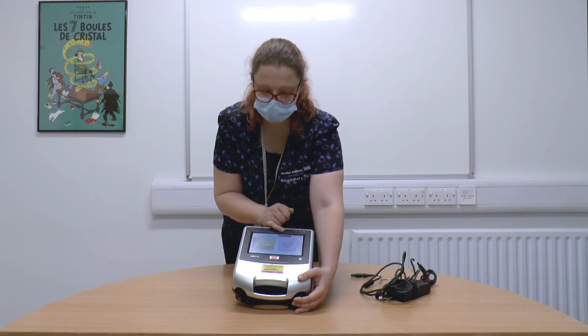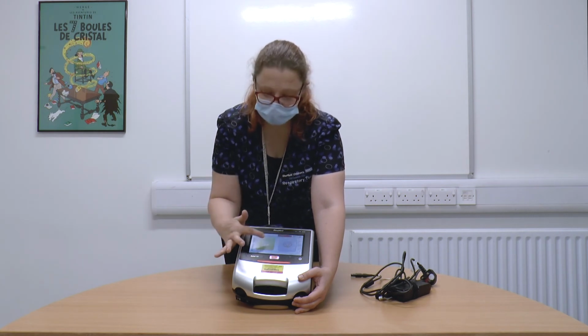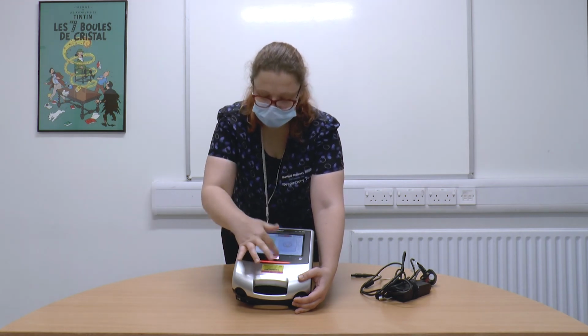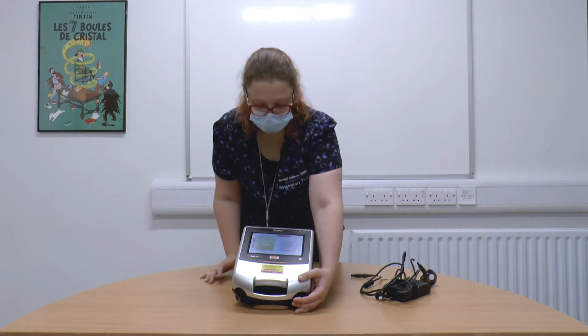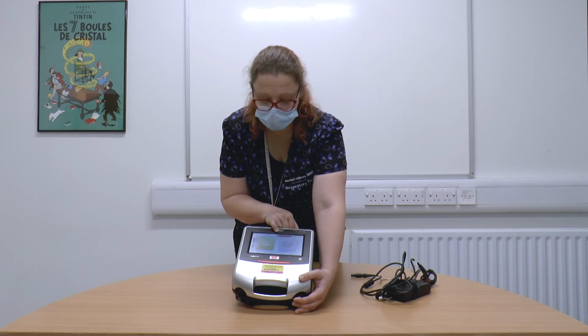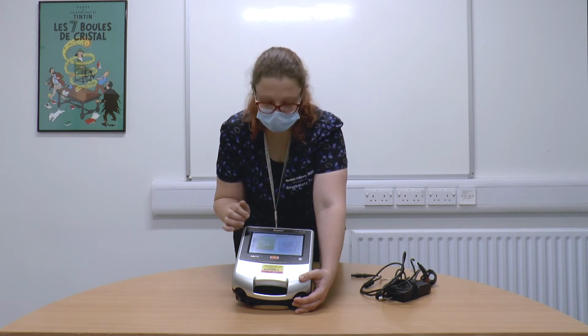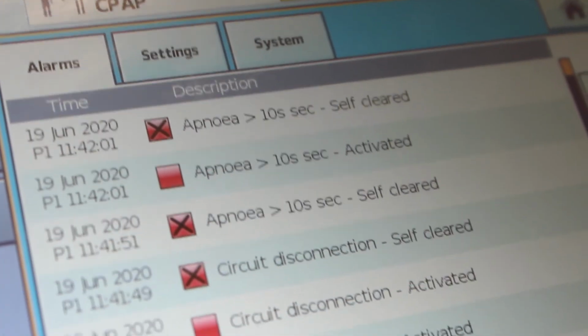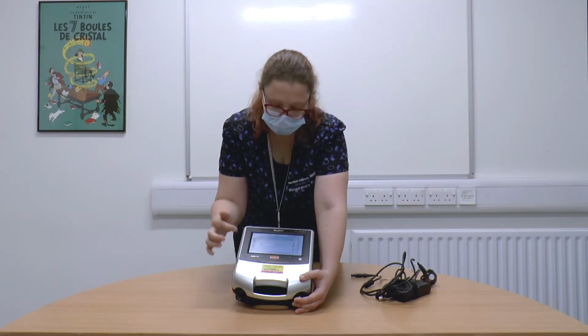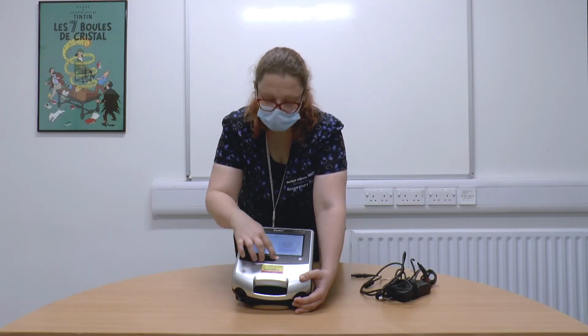As you can see, if any alarm goes off, either a red bar appears up here and a red light. I can silence it on the screen, or I can silence it on the ventilator. Until I have solved the problem, it will continue to flash red. You can see in the centre of the screen, because I have silenced it, an orange bell has appeared. That will stay silent for 30 seconds to allow me to solve the problem. If lots of alarms have occurred, I can click on the top bar. It will show me all the alarms that have happened. To remove them all, I can press reset all, OK, and it will clear everything.